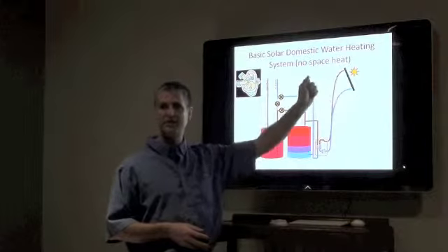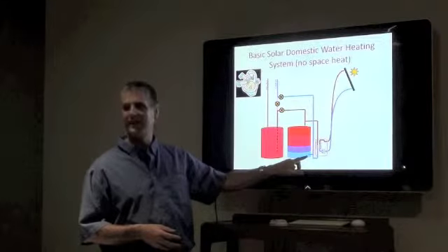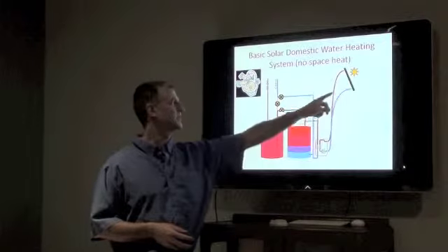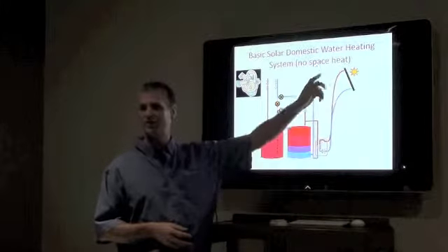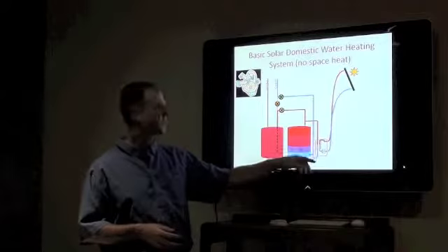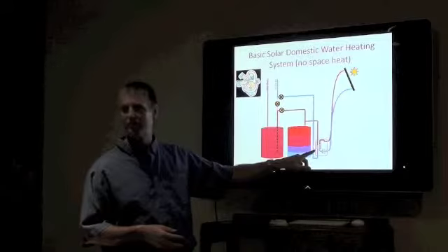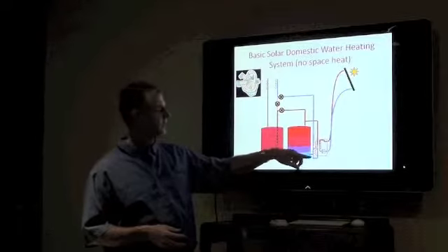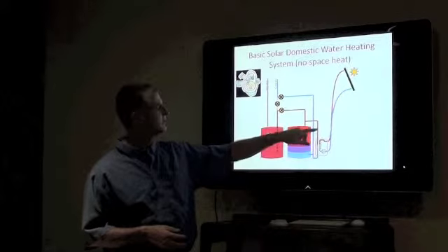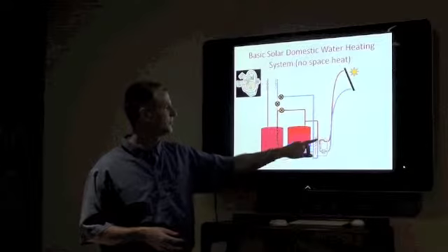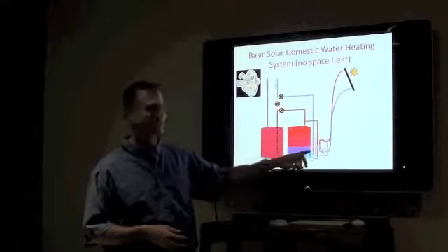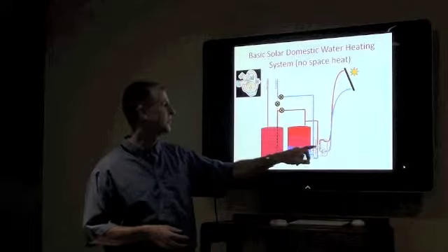The solar collector has a temperature sensor in it. When it's hotter in the solar collector than at the bottom of this tank, the pump runs. That brings heat from the solar collector through this heat exchanger and back up to the collector. On the other side of the heat exchanger, cold water enters the bottom. It's heated by the glycol flowing through the heat exchanger, and this heated water then rises up into the top of the tank. So a thermal siphon loop is established in the tank as long as the temperature in the heat exchanger is hotter than the water coming into the bottom of the heat exchanger.